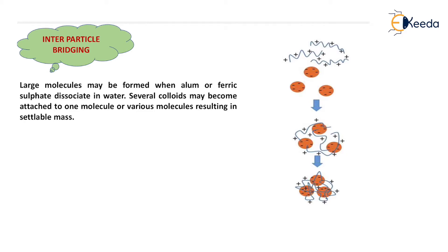The fourth mechanism is inter-particle bridging. Large molecules may be formed when alum or ferric sulfate dissociate in water. Several colloids may become attached to one molecule or various molecules, resulting in a settleable mass. When positive charge is added in water, some negative charge will come in contact with the positive and it will form that type of molecule. When this type of molecule forms, charge neutralization takes place. Due to the neutralization of the charge, colloids come in contact with each other and grow in size, resulting in settleable mass. That is inter-particle bridging, the fourth mechanism of coagulation.